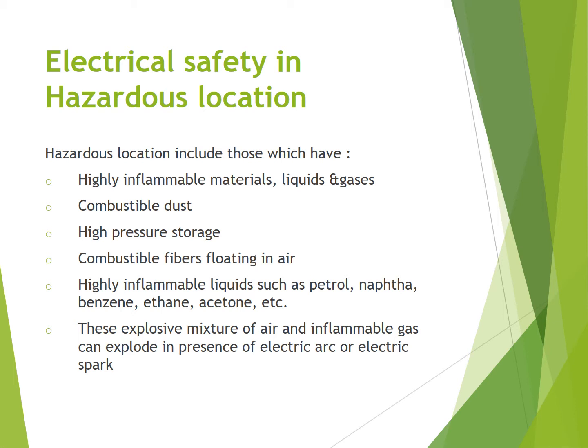This hazardous location includes highly flammable materials, liquids, gases, combustible dust, combustible fibers, and inflammable liquids such as petrol, naphtha, benzene, ethane, butane, propane. All these are considered to be inflammable gases. Places where those inflammable gases are present, we can consider as hazardous zone.